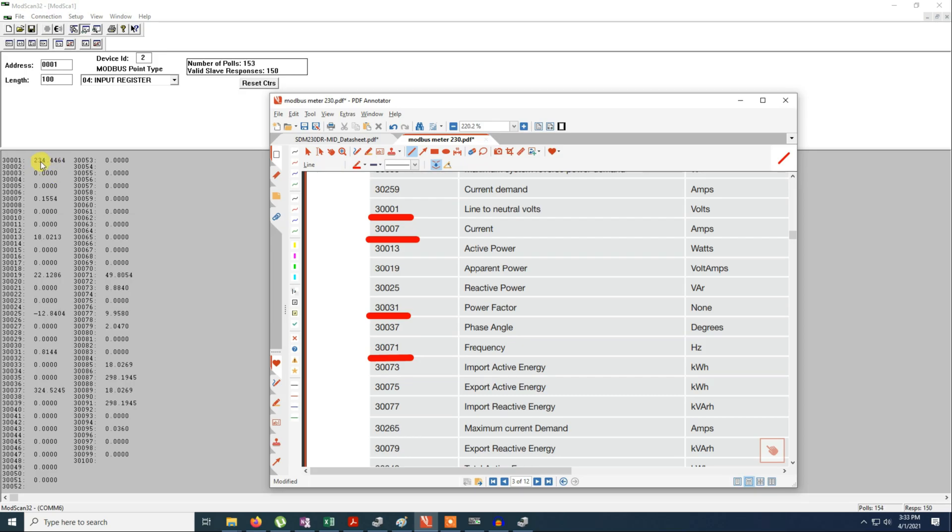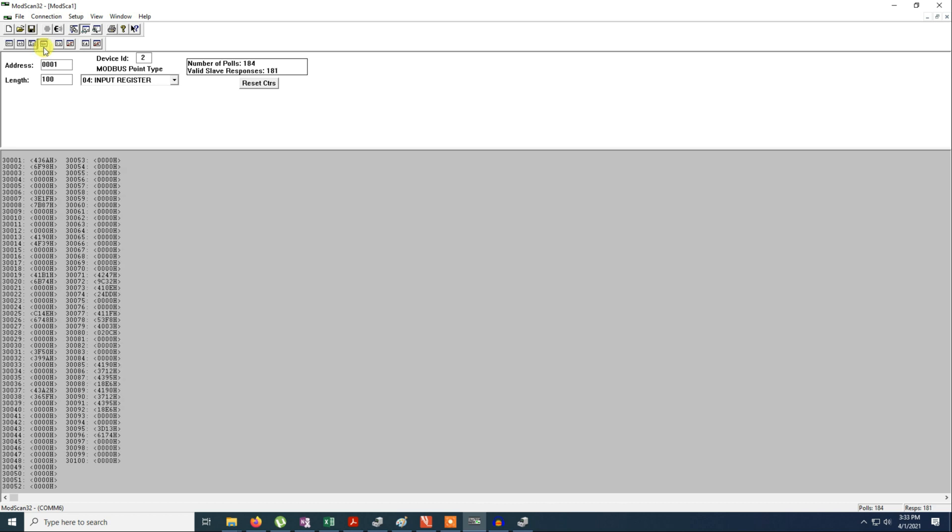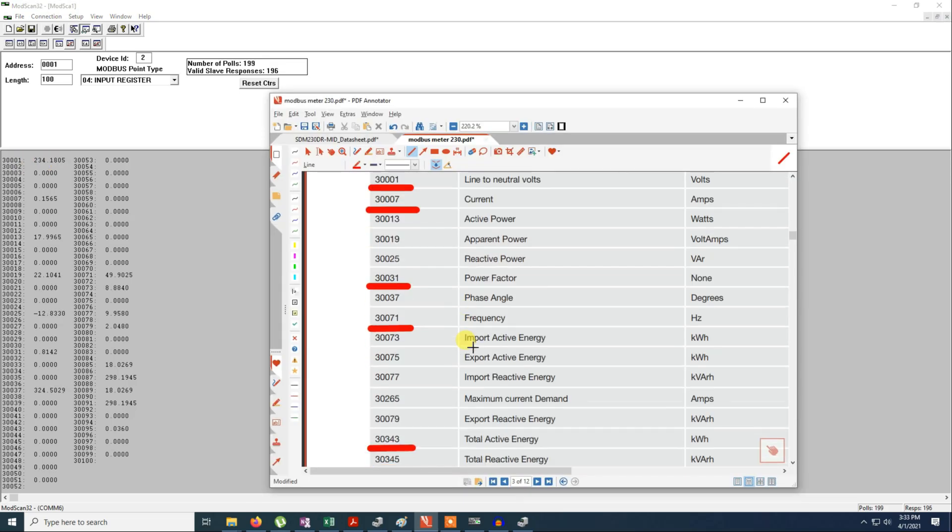Because in fact to display this voltage it's using two registers. Yeah I forgot to tell you, you should also select the float type. Because if you don't select the float type the voltage won't be displayed properly. Because you see you will have value in hex. So float, what will happen? It will take two registers, address 1 and address 2. So for the frequency 30071, here. So here is the frequency.